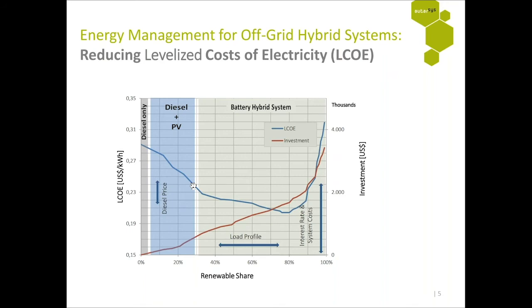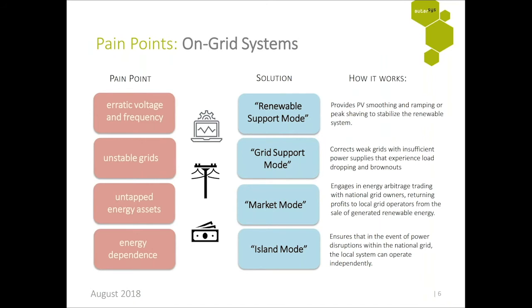So you have to implement batteries, and this becomes a question of optimizing the economic cost — you have to look at the price of fuel, the price of your storage and photovoltaic system, and the financing costs over time. These elements together have to be simulated to get the optimal solution, which is normally somewhere around 80%, shown here as the lowest price per kilowatt hour, the levelized cost of electricity. That's basically what rural electrification systems, or systems for small or slightly bigger islands, are doing — and that's, in the meantime, the success story of battery solutions or hybrid solutions, the combination of PV power and batteries.